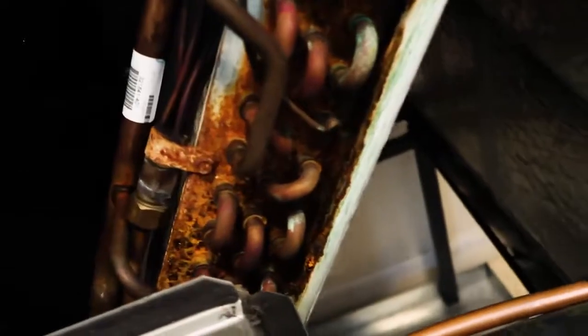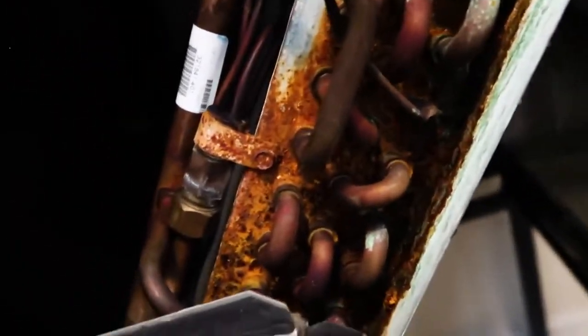I never underestimate the visual inspection. This unit is a 2014 — it's only four years old — and you can see there's a lot of galvanic corrosion, which isn't necessarily a big deal, but of course it looks awful.